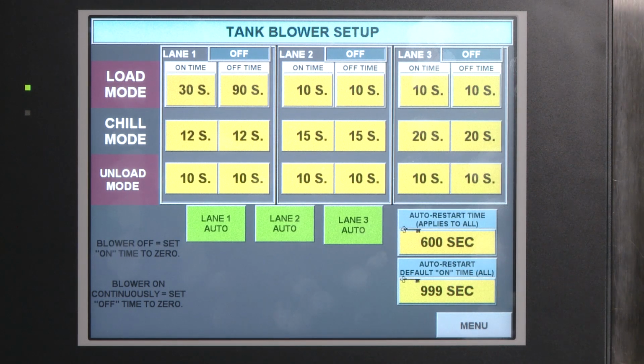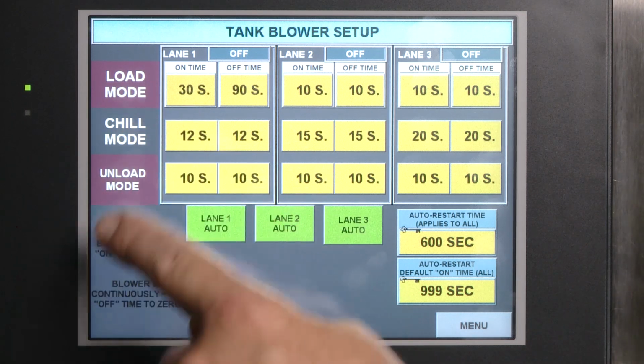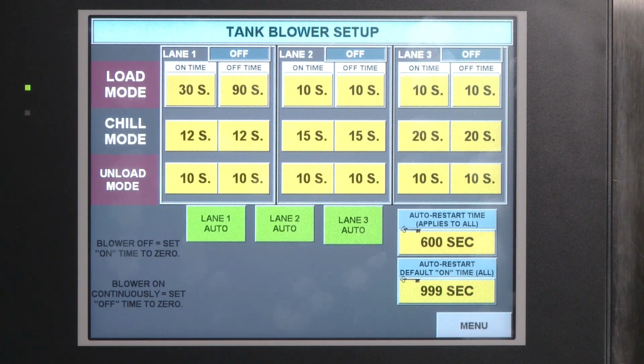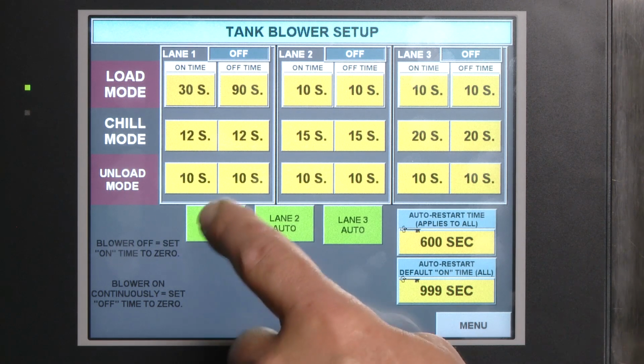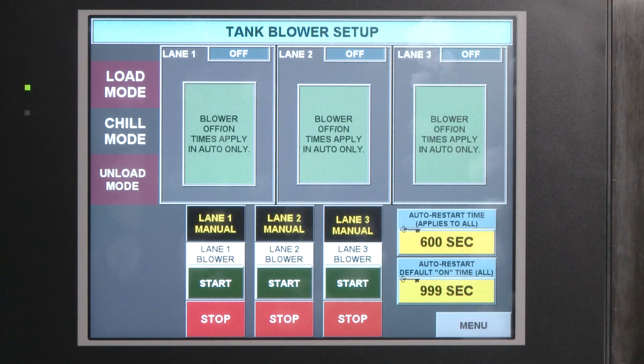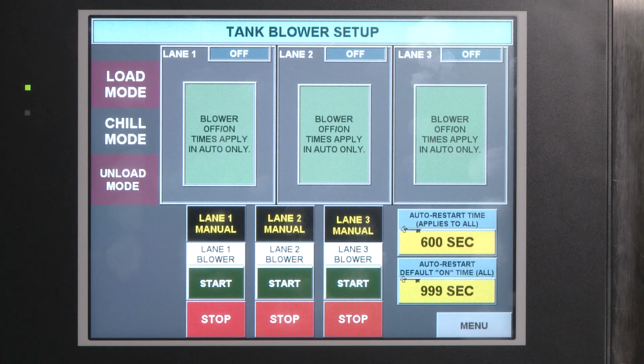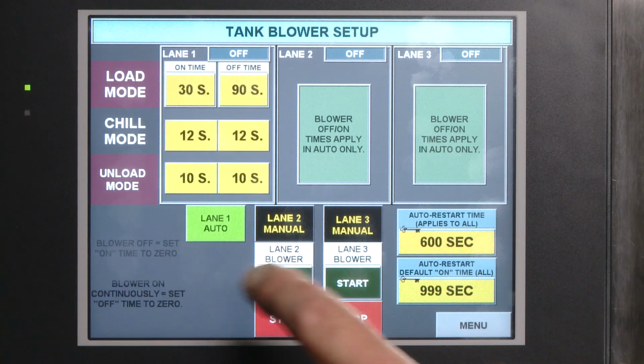A different on-off interval may be defined for the load mode, chill mode, and unload mode. In addition, each lane may be defined separately. When in manual mode, the blower can be started and stopped at will. In manual, the blower times will not be displayed, and the start-stop buttons will be displayed. In auto, it will run per the set timer values.